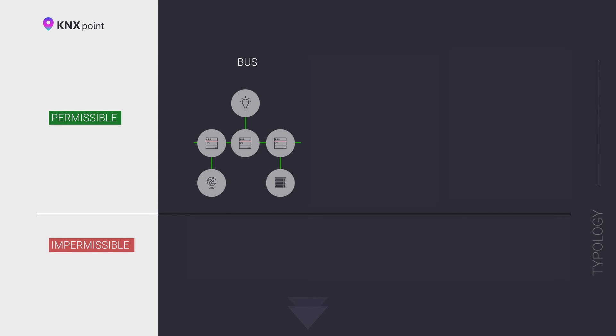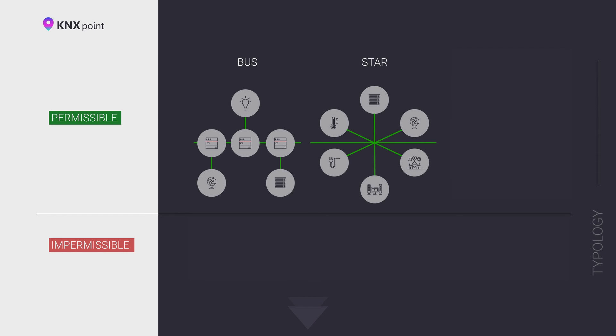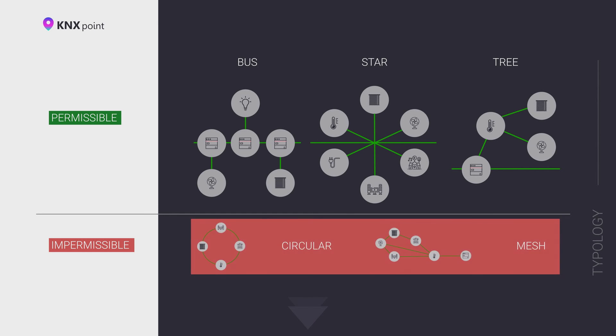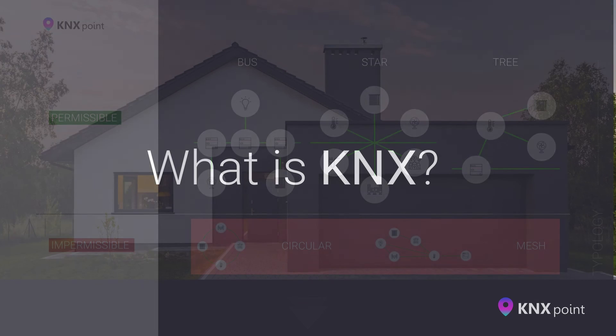The KNX bus topology can have the following branching types. First, serial connection. Second, star connection. Third, tree connection. All these options can be combined on any section of the line. The formation of loop topologies is strictly prohibited on any section of the bus.